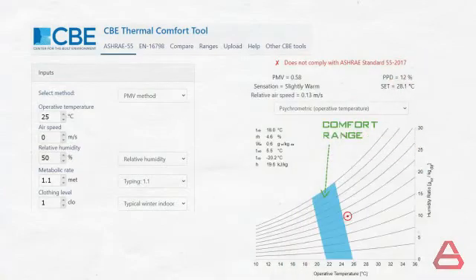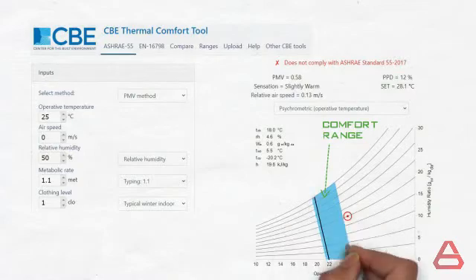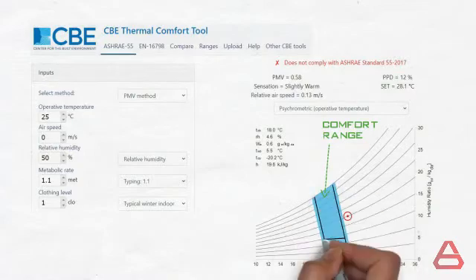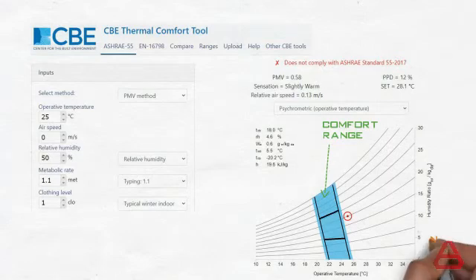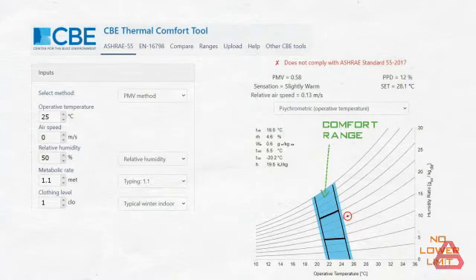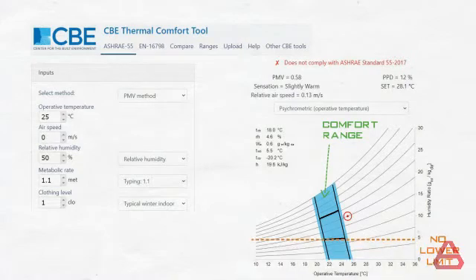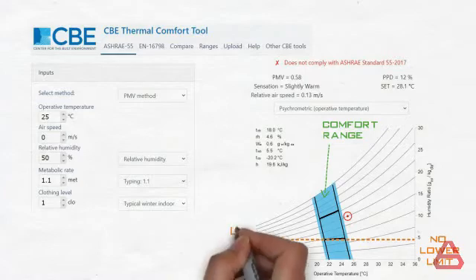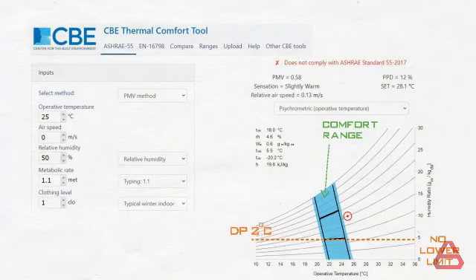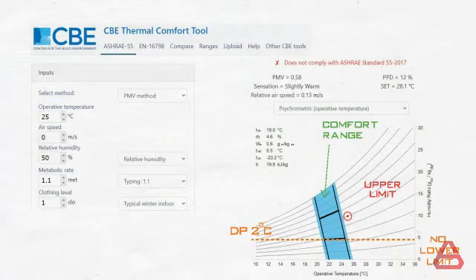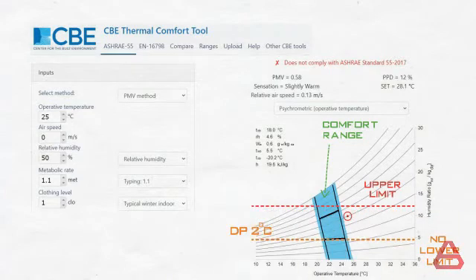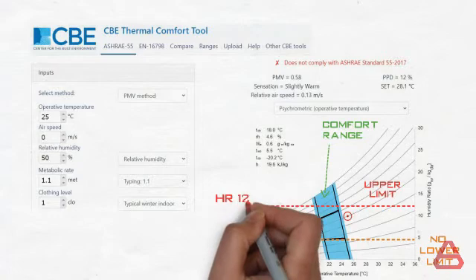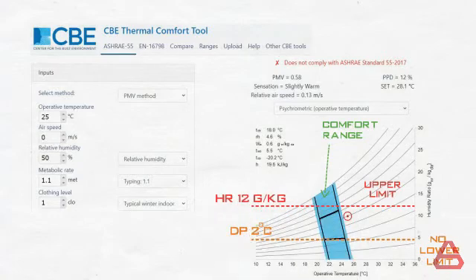From this range, any point can be selected, but I try to stay away from borderline temperatures and very low or high humidity values. Although there is no lower limit to humidity according to the ASHRAE standard 55, there is a recommendation to stay above a dew point temperature of 2 degrees Celsius. For the upper limit of humidity, ASHRAE recommends staying below a humidity ratio of 12 grams of water per kilogram of dry air.